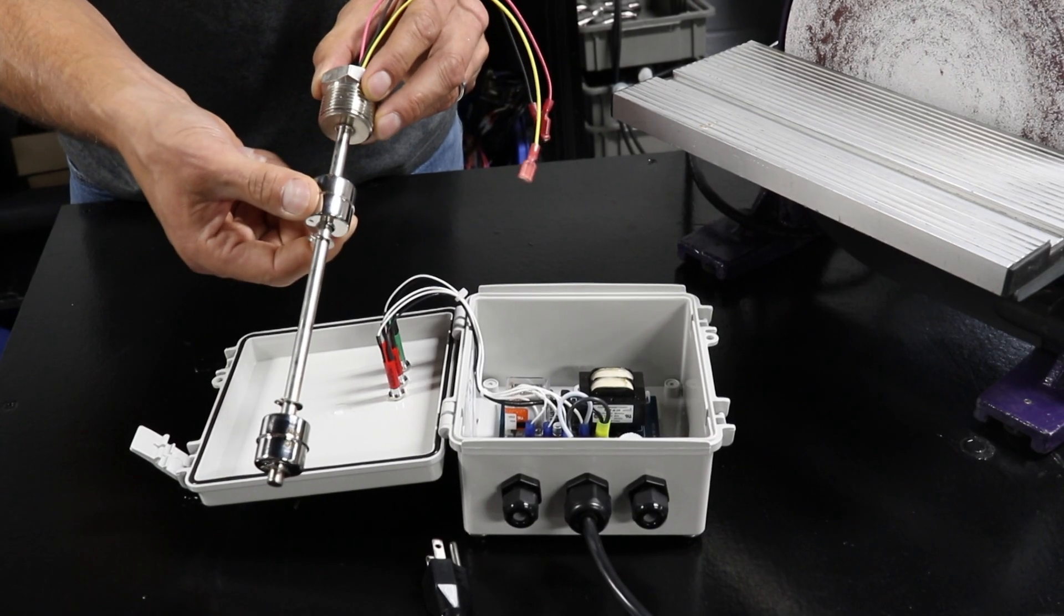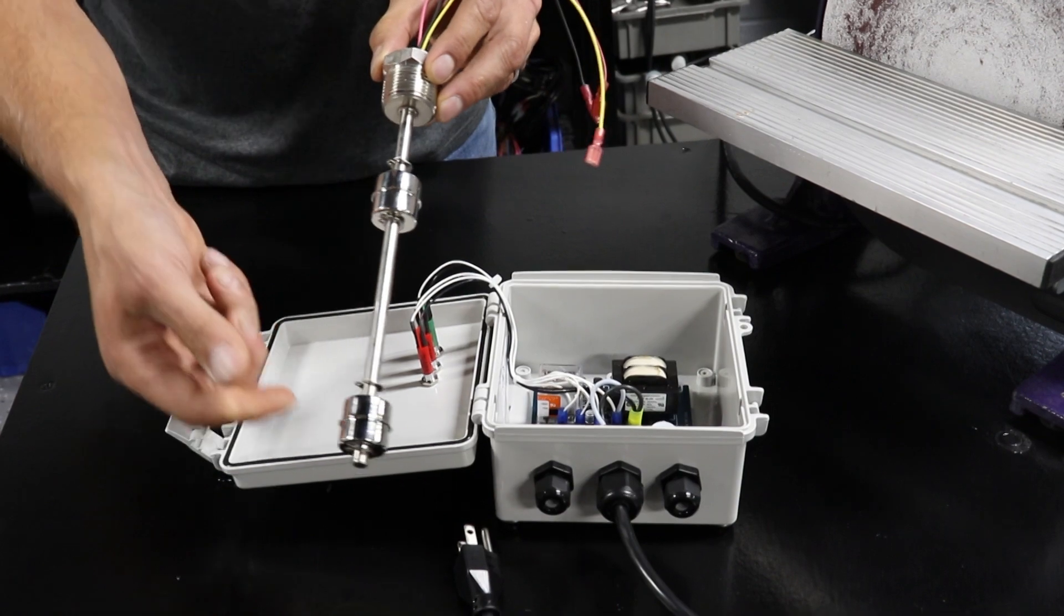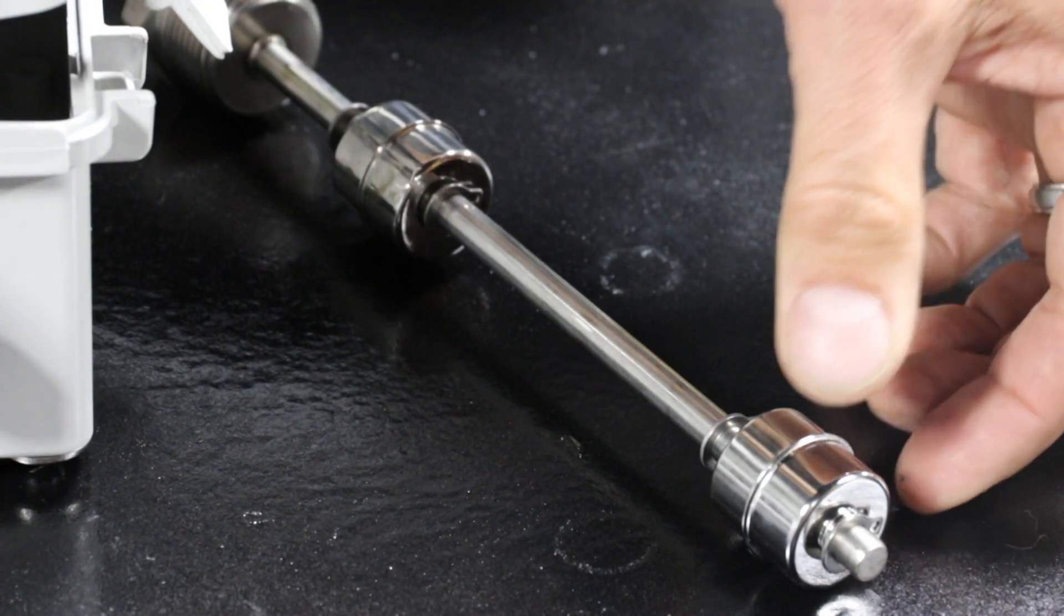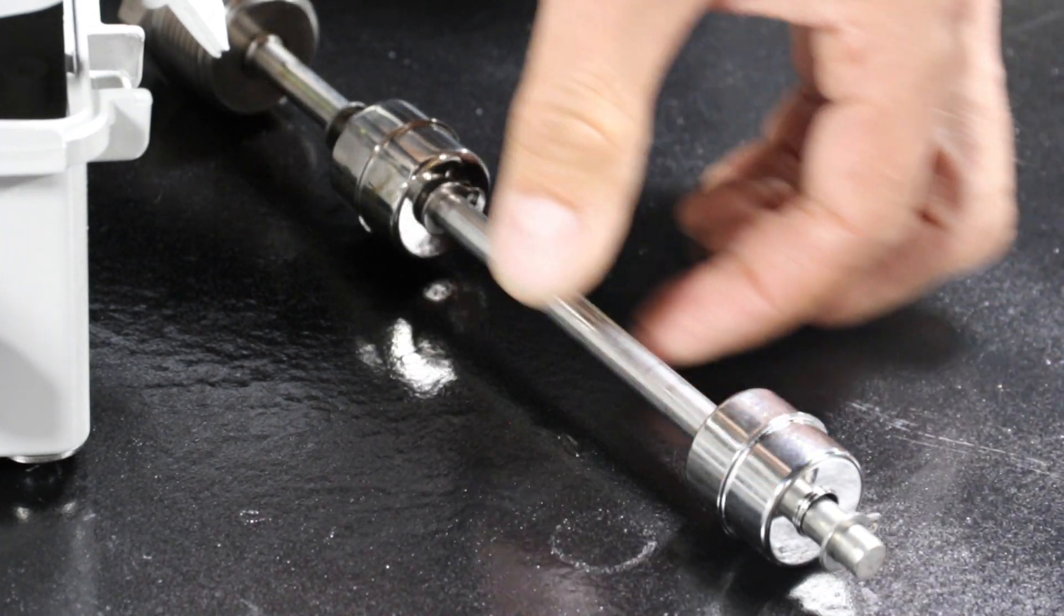It requires the use of two separate float switch positions. One is for high level and one for low level. The float switches can be two individual single level floats or a single shaft multi-level float switch.